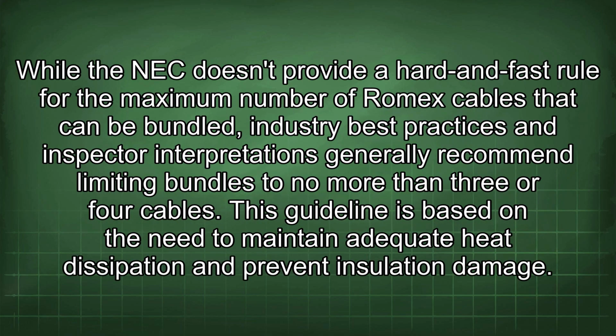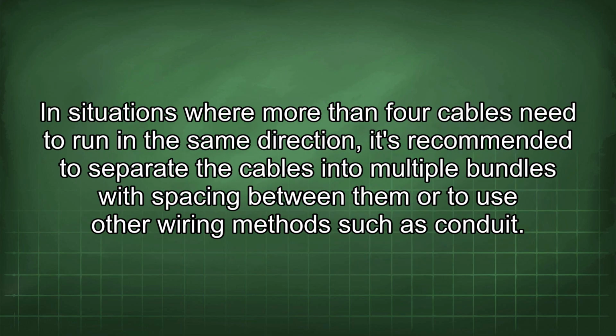While the NEC doesn't provide a hard and fast rule for the maximum number of Romex cables that can be bundled, industry best practices and inspector interpretations generally recommend limiting bundles to no more than 3 or 4 cables. This guideline is based on the need to maintain adequate heat dissipation and prevent insulation damage. In situations where more than 4 cables need to run in the same direction, it's recommended to separate the cables into multiple bundles with spacing between them or to use other wiring methods such as conduit.